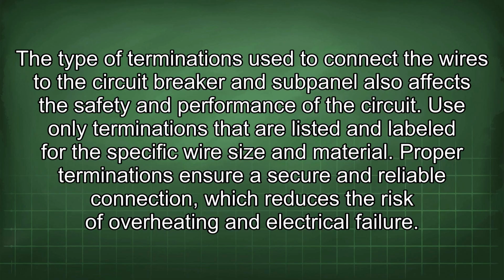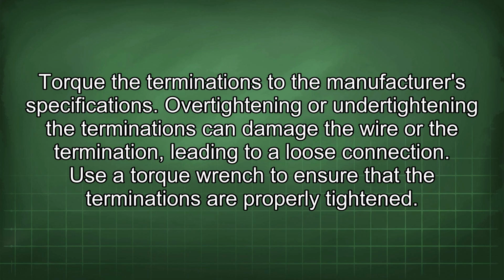The type of terminations used to connect the wires to the circuit breaker and subpanel also affects the safety and performance of the circuit. Use only terminations that are listed and labeled for the specific wire size and material. Proper terminations ensure a secure and reliable connection, which reduces the risk of overheating and electrical failure. Torque the terminations to the manufacturer's specifications. Over-tightening or under-tightening the terminations can damage the wire or the termination, leading to a loose connection. Use a torque wrench to ensure that the terminations are properly tightened.